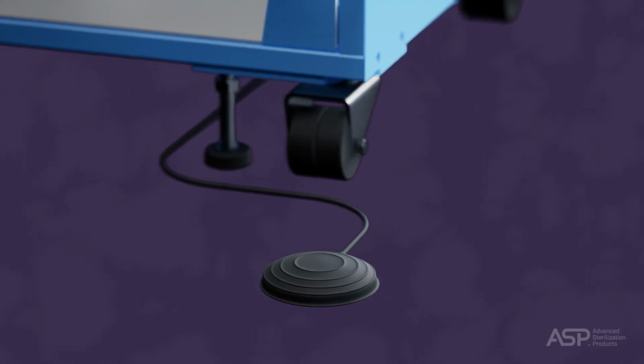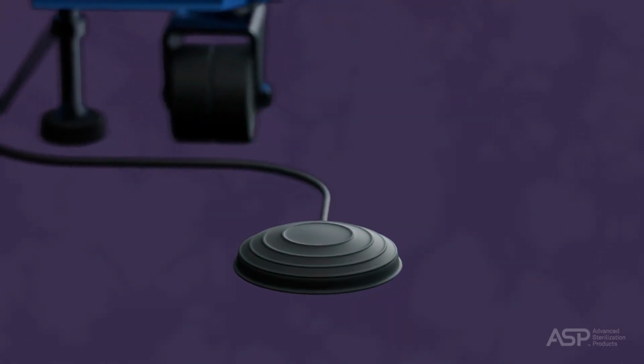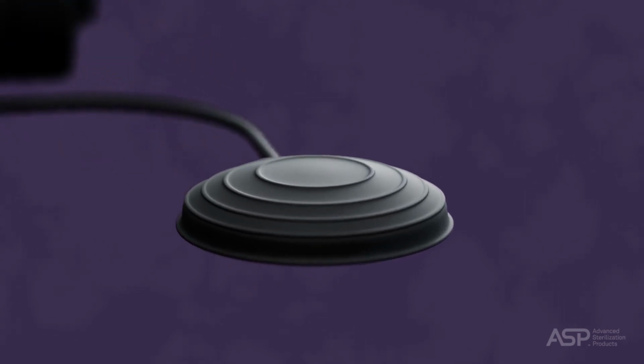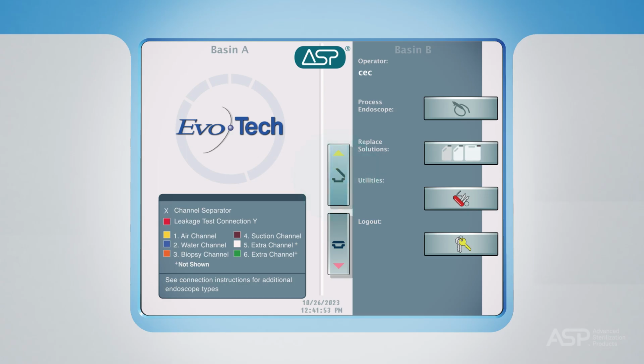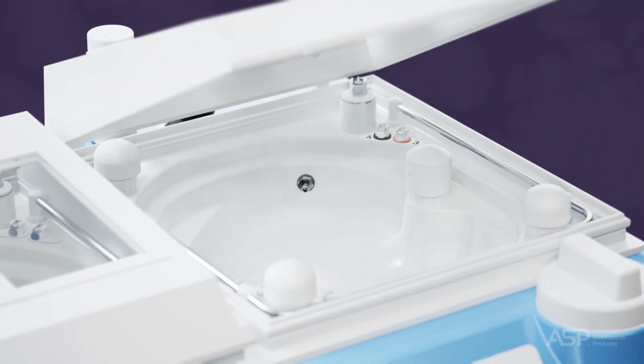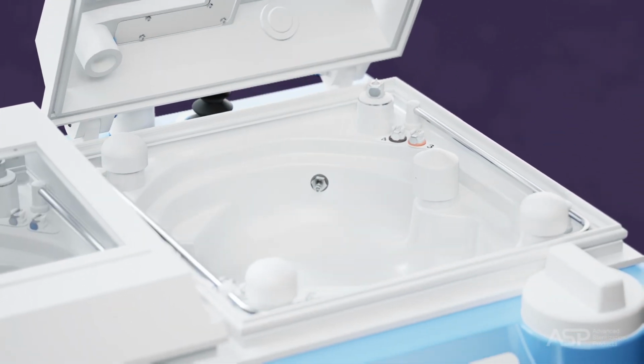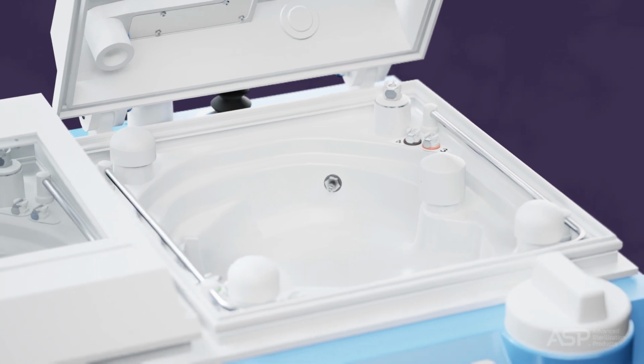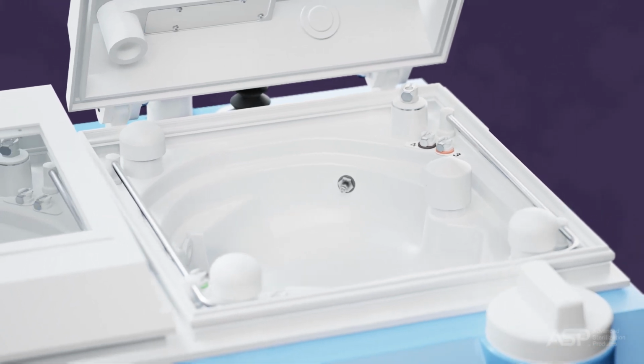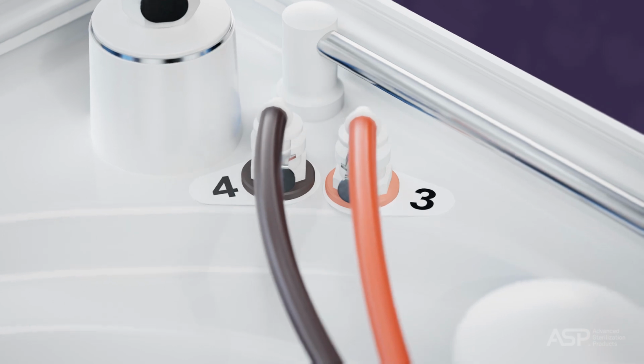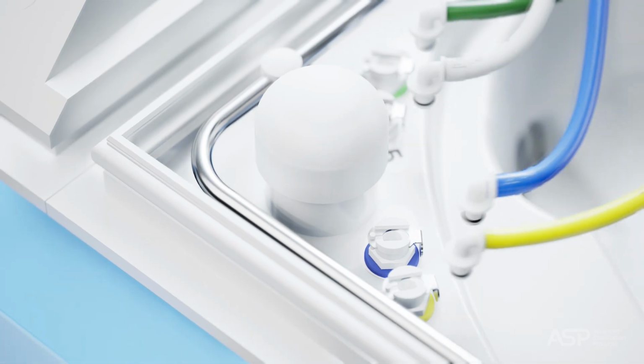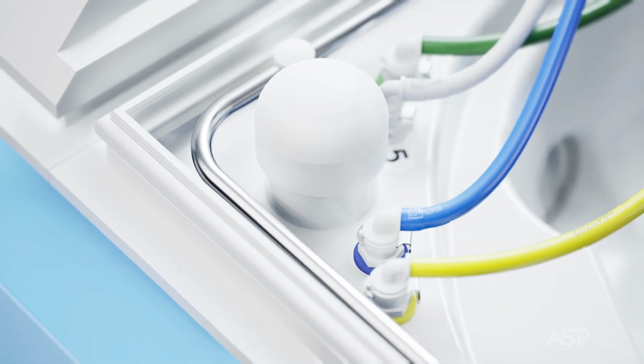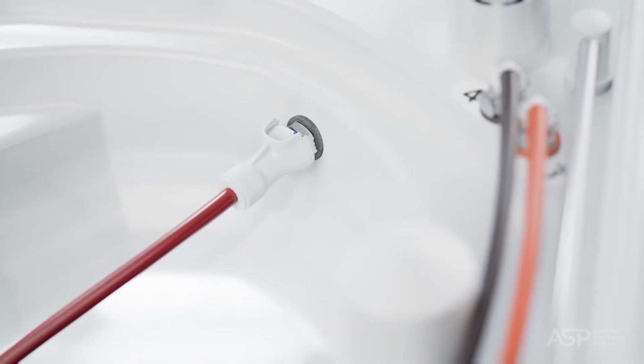To open the EVOTECH ECR lid, step on the foot pedal of the side you wish to use for 1 second or use the touchscreen button with clean hands or gloves. To connect your endoscope to the basin, snap the color-coded connectors into the corresponding color-coded ports on the EVOTECH ECR basin. The brown connector will fit into the black port. Confirm that you hear and feel a click to verify the connectors are fully snapped properly into the basin.